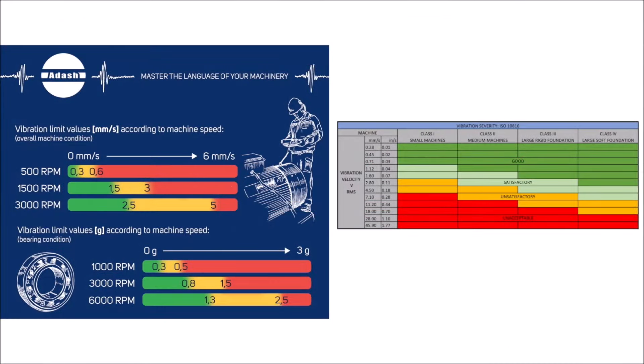Whether we use ISO or ADASH vibration limit values, they are just informational. You should always try to find out what the vibration limit values for your particular machine are. In other words, to find out what the optimal operational condition of your machine is. You can do that by measuring and comparing more machines of the same type, running at the same speed and under the same load. Or, you can ask a vibration diagnostician, who should be able to make a deeper analysis of the machine, and tell you if the machine is running under its optimal condition.